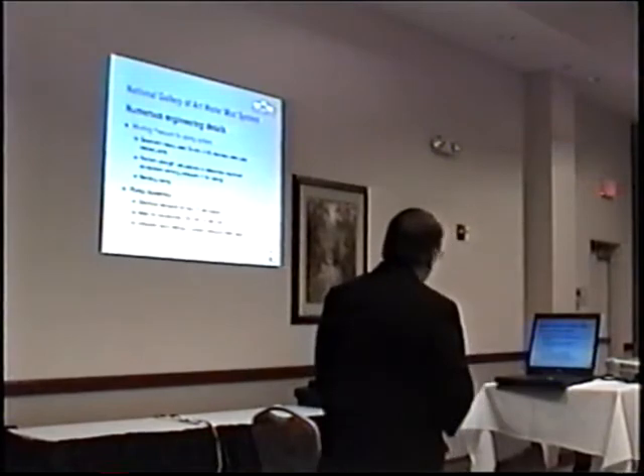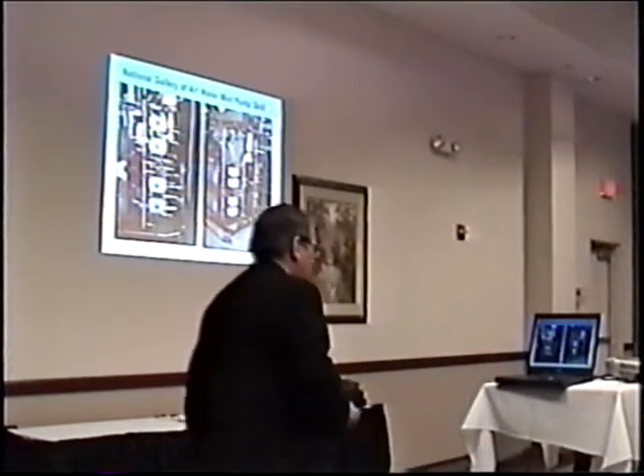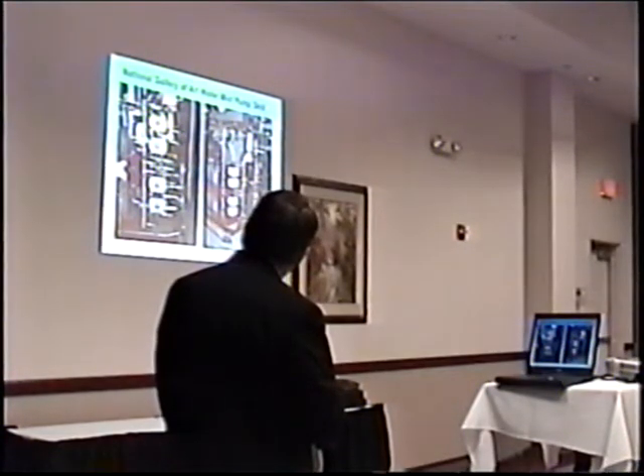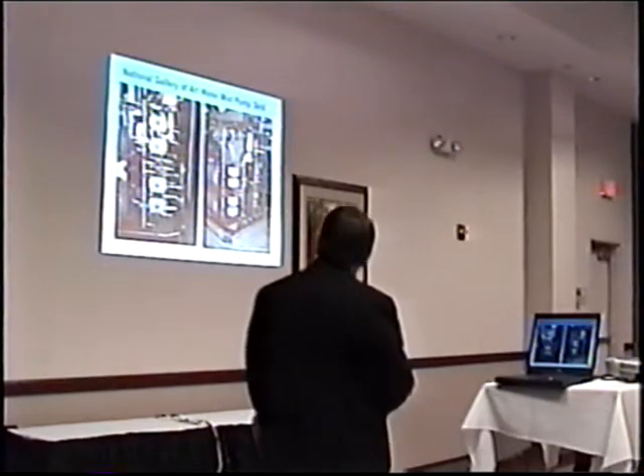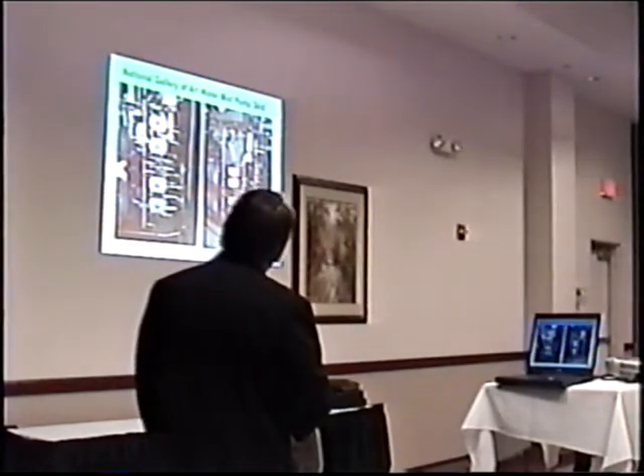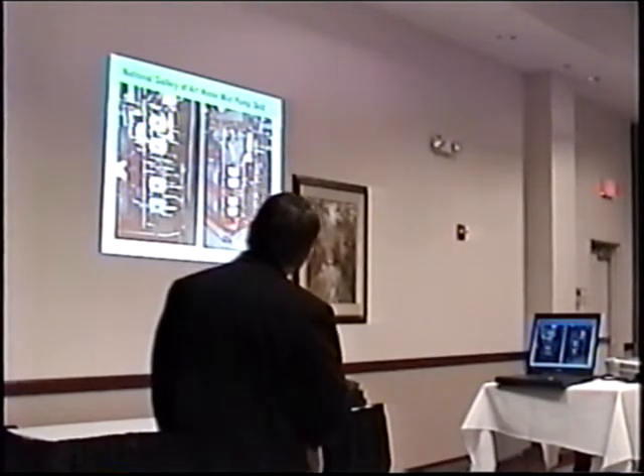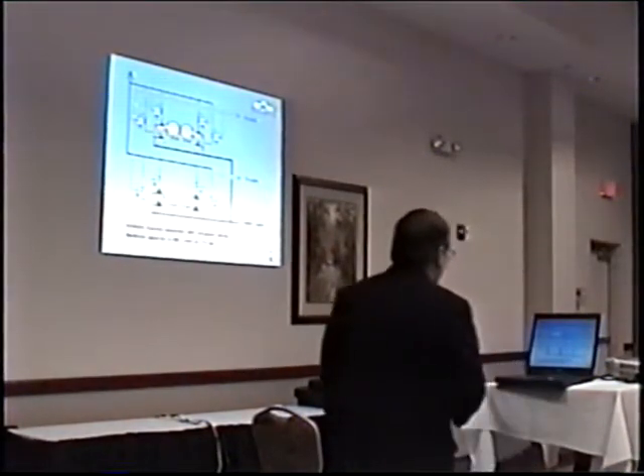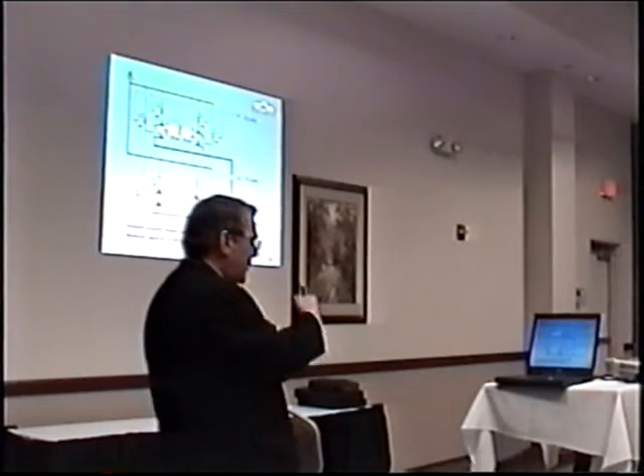For high pressure water mist pumps using positive displacement pump concept, they need things called unloader valves, which I'll talk a little bit about. Here's the pump assembly in the basement. 1, 2 motors on this side, and there's 2 around the other side. There's 2 pumps per motor. These are the small pumps. They're about 13 gallons per minute each, 49 liters per minute. And each one has its own unloader valve. Here's 2 unloader valves. There's an unloader valve down there. So an unloader valve works to, because it's a positive displacement pump, it's trying to push a piston of water out of the chamber.